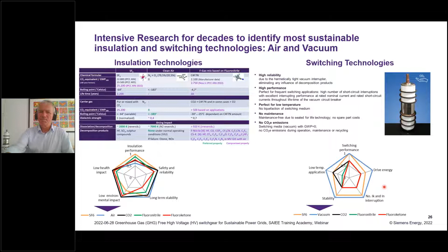So from our perspective, the blue one is the best overall solution, although it has the lowest insulation performance. On the right-hand side, you see the same for switching technologies, again with different colors: switching with SF6, switching with vacuum in blue, black CO2 switching, green fluoronitrile switching, and red fluoroketone switching. Here, from our perspective, it's very clear that vacuum interrupter technology is the strongest switching technology, also compared to SF6.